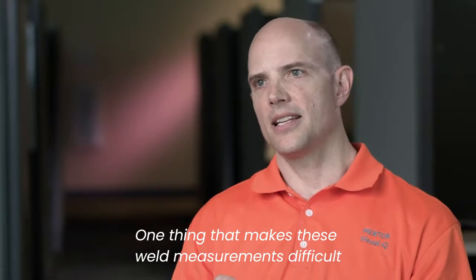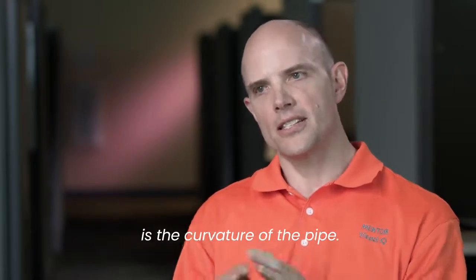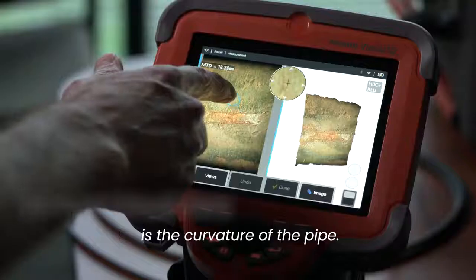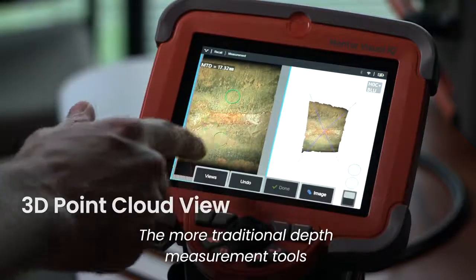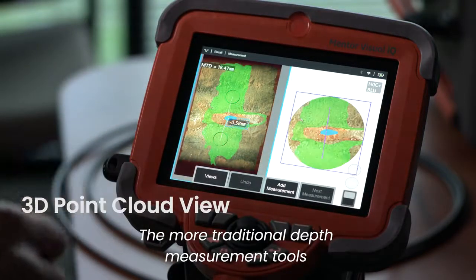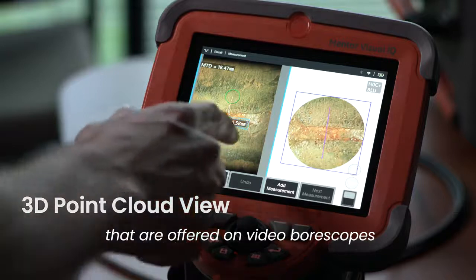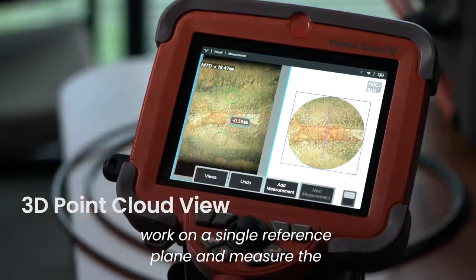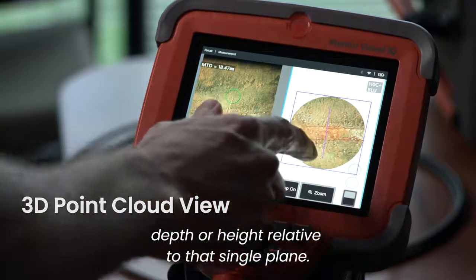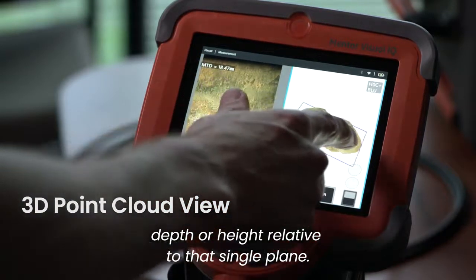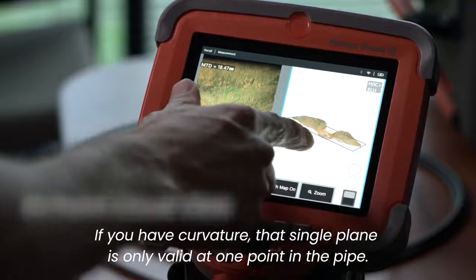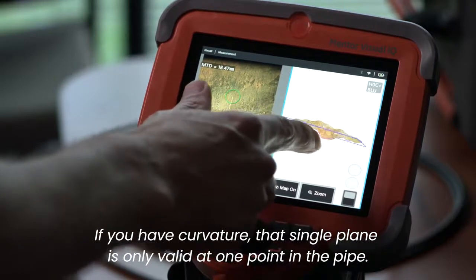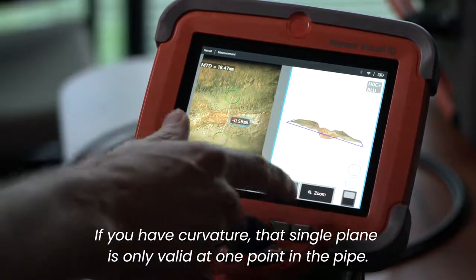One thing that makes these weld measurements difficult is the curvature of the pipe. The more traditional depth measurement tools that are offered on video borescopes work on a single reference plane and measure the depth or height relative to that single plane. If you have curvature, that single plane is only valid at one point in the pipe.